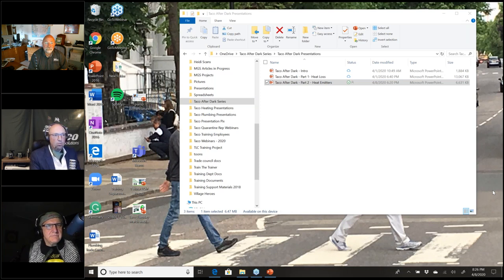And if we do the heat loss, we're going to see the numbers are lower than we've ever seen before, or expected it to be. Expected, yeah. What we thought it was going to be. And now the DHW load is larger. So if we can get that boiler on reset, and when there's a DHW call, let's get that thing up to high fire after that. So those are my thoughts here on the East Coast.